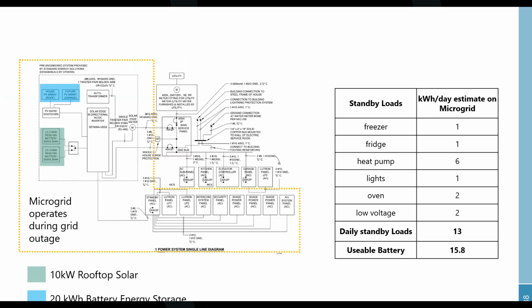This allows the home during grid outages, when the utility fails in Arlington, to allow the home and owner to maintain key electrical loads in the property, including fridges and freezers, their heat pump, lighting, minimum low voltage, as well as a warming or small oven, and support that operation during the grid outage. So we did some analysis on daily electricity consumption anticipated from that smaller standby panel, as well as what we would be generating from the rooftop solar and what we could store on site.